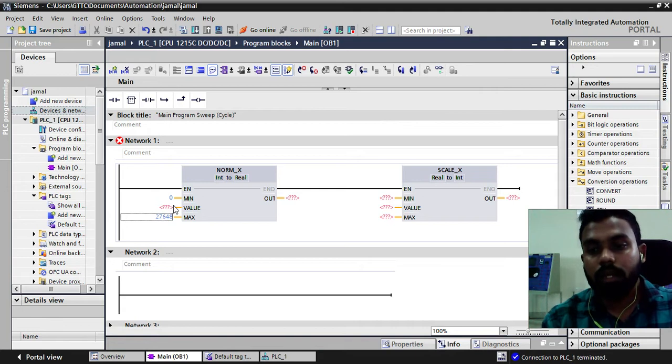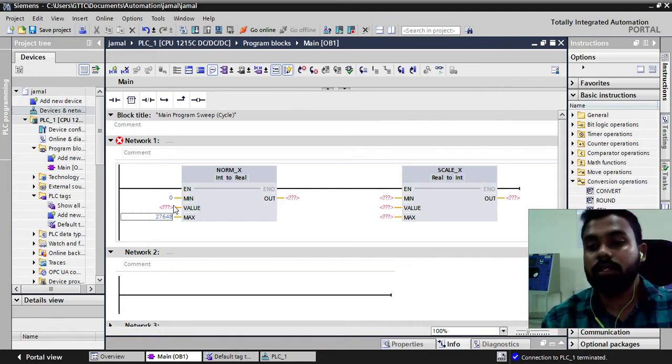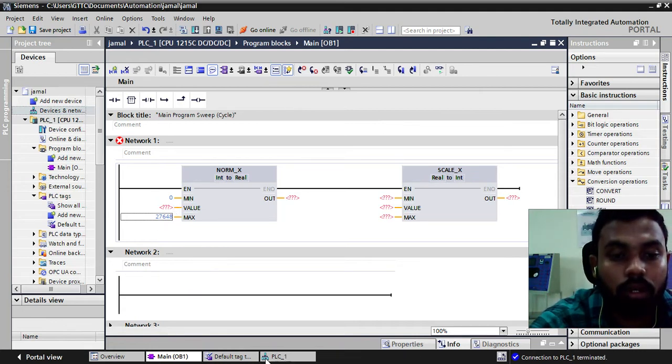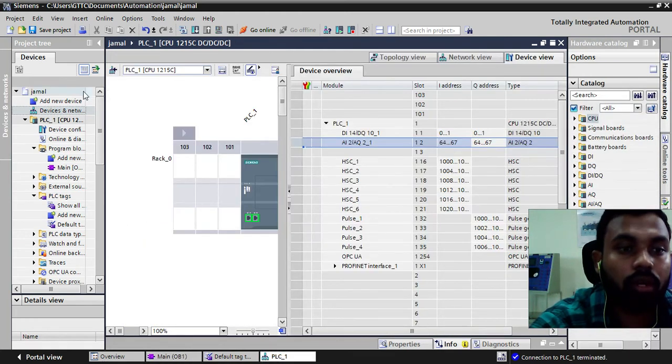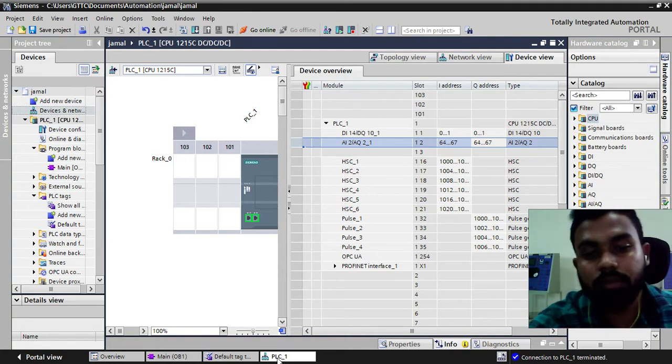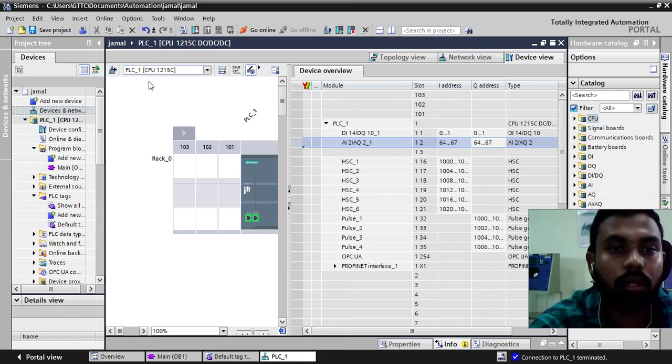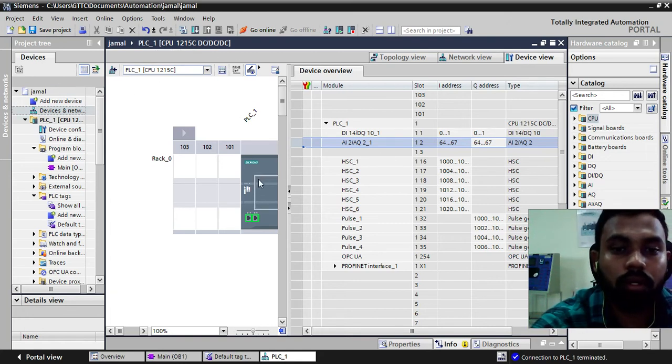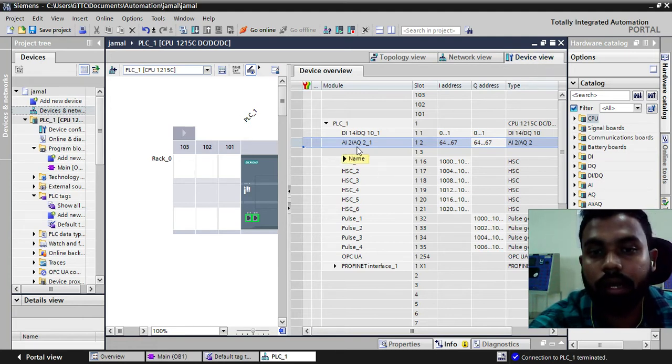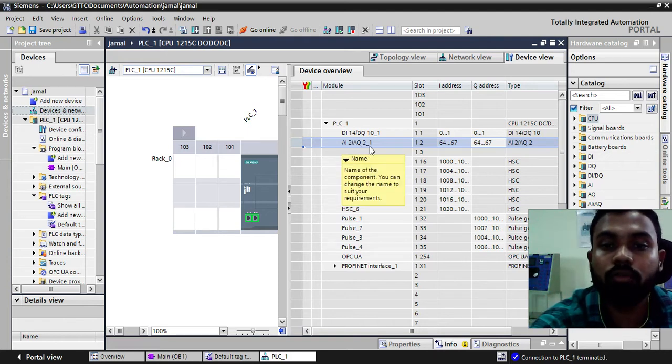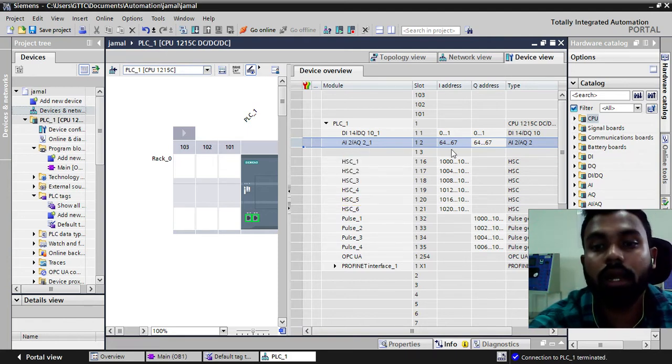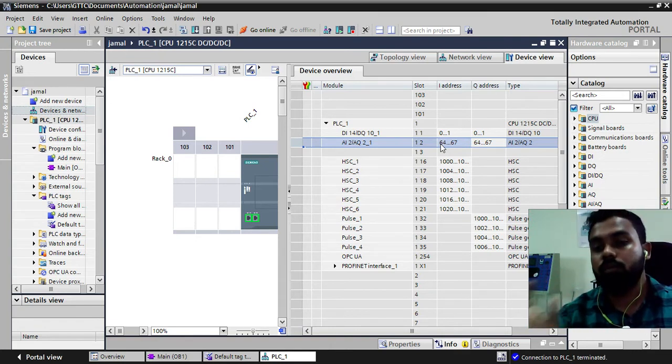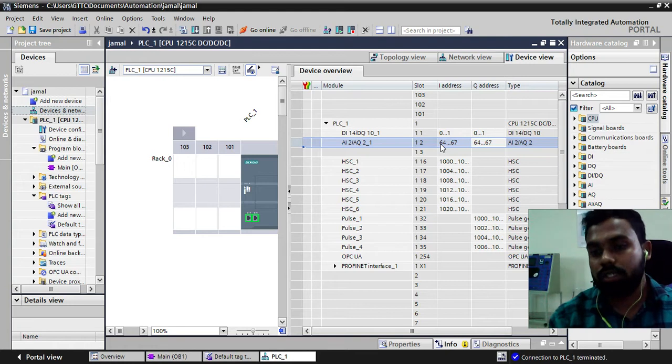We have certain addresses. How you can know that which address from which address we are going to get the analog input. Just go to PLC. You can go from here also device and network. As I have opened this previously you can click on this. You can find PLC CPU 1215C here. In that just go to device view. In the device view you can find AI2 AQ2. That means two analog inputs and two analog outputs. And the addresses of those analog inputs and outputs are from 64 to 67.